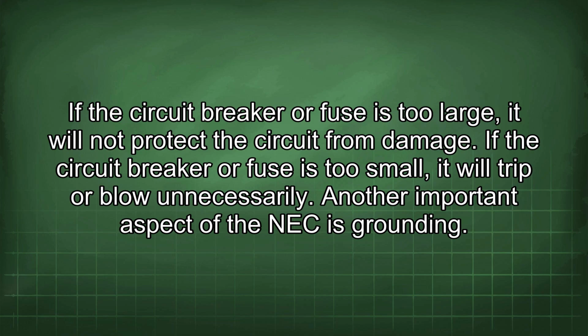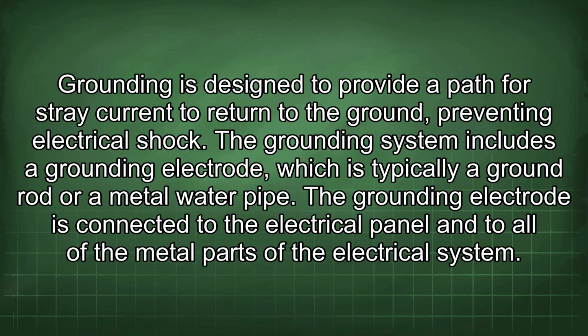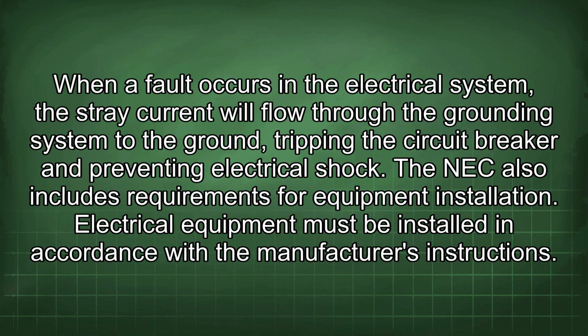Another important aspect of the NEC is grounding. Grounding is designed to provide a path for stray current to return to the ground, preventing electrical shock. The grounding system includes a grounding electrode, which is typically a ground rod or a metal water pipe. The grounding electrode is connected to the electrical panel and to all of the metal parts of the electrical system. When a fault occurs in the electrical system, the stray current will flow through the grounding system to the ground, tripping the circuit breaker and preventing electrical shock.